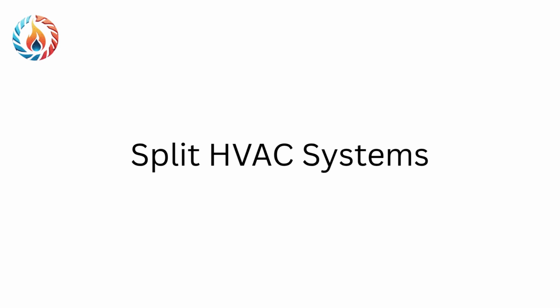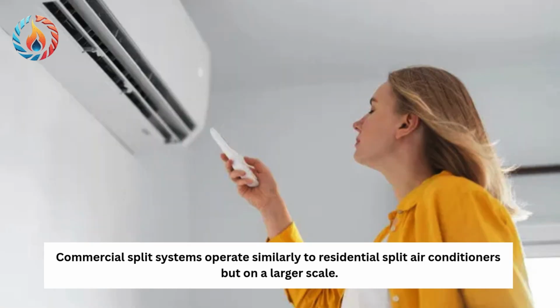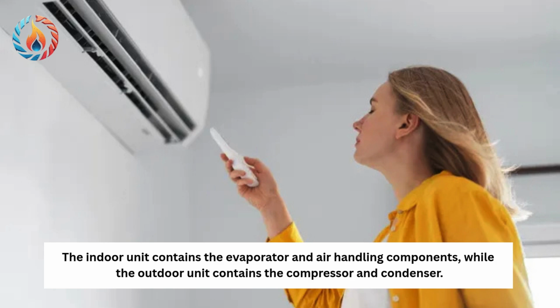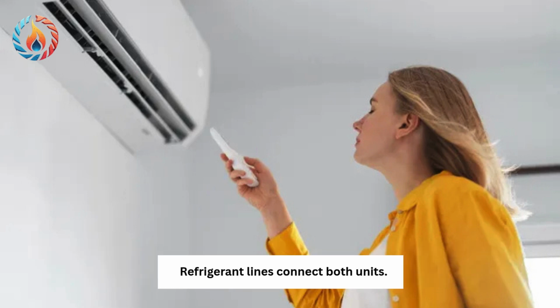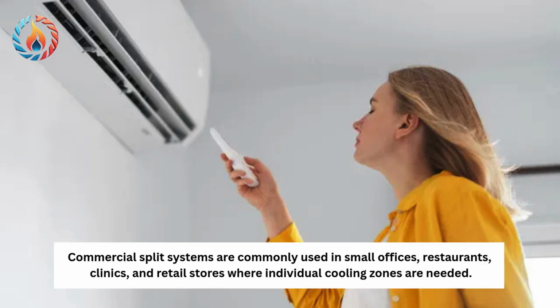Split HVAC systems. Commercial split systems operate similarly to residential split air conditioners, but on a larger scale. The indoor unit contains the evaporator and air handling components, while the outdoor unit contains the compressor and condenser. Refrigerant lines connect both units. Commercial split systems are commonly used in small offices, restaurants, clinics, and retail stores, where individual cooling zones are needed.